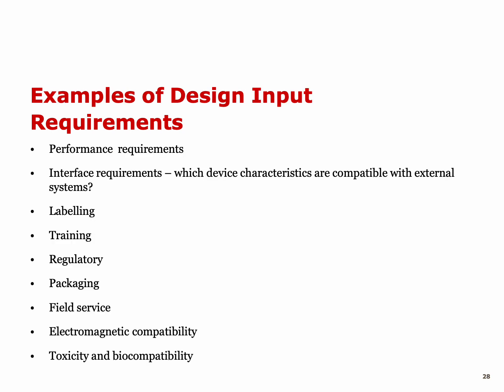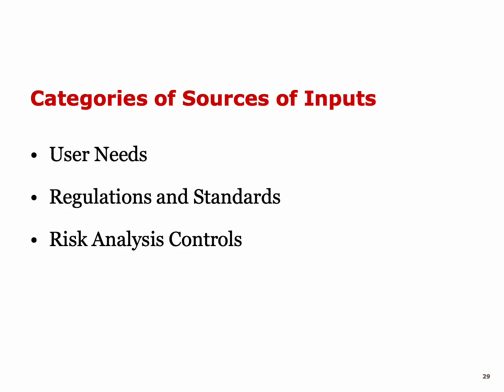Now talking about the example of design inputs, so we can talk about documents on performance requirements, on interface requirements, on labeling, on trainings, on regulatory, packaging, field service, electromagnetic compatibility, toxicity, and biocompatibility. So these are all different elements that may be in a design input document.